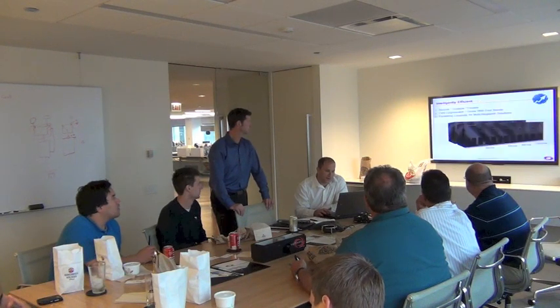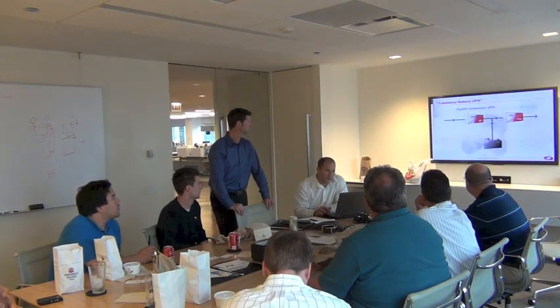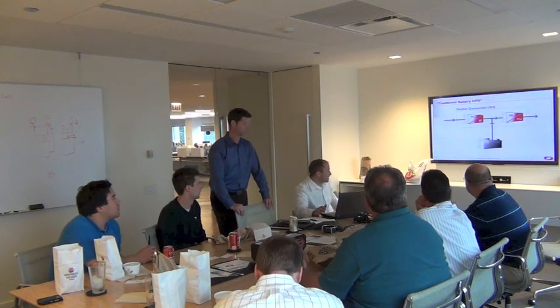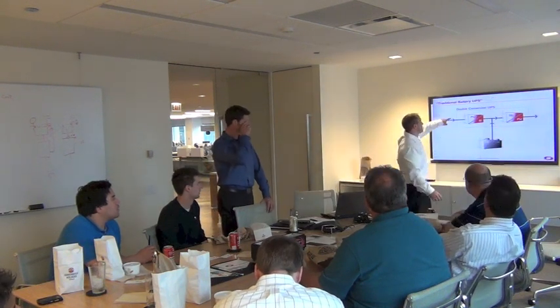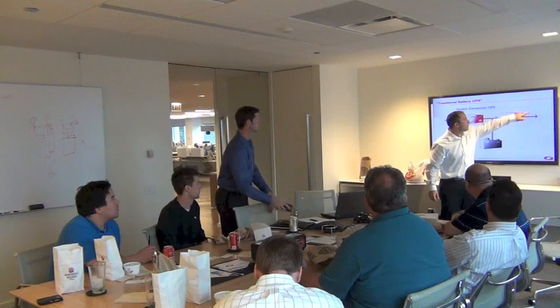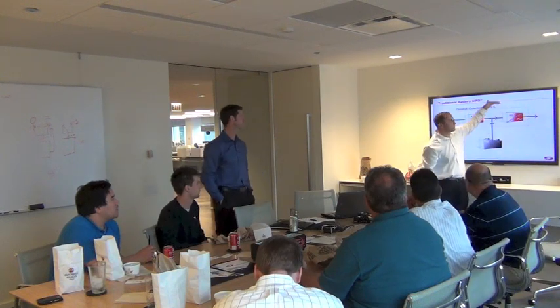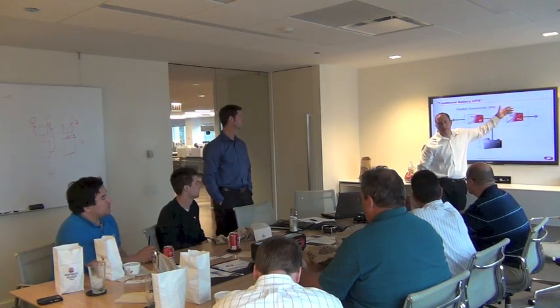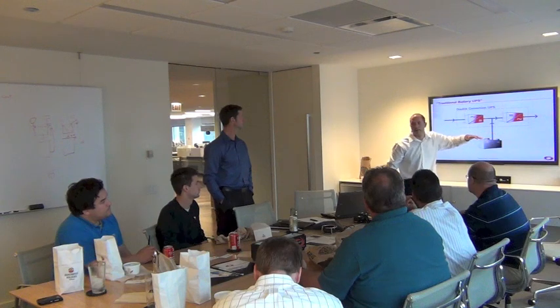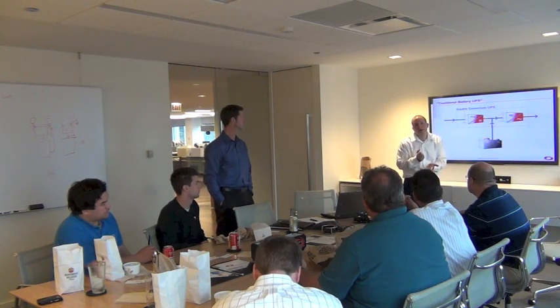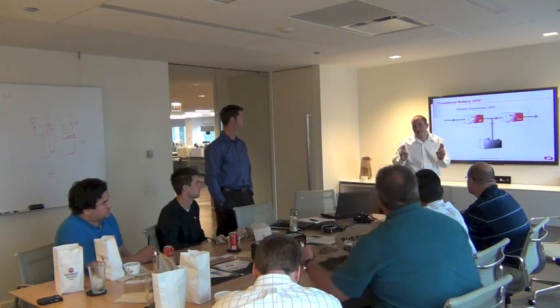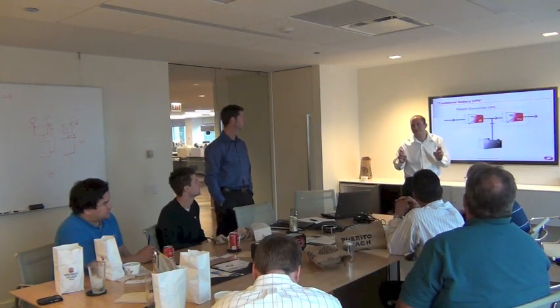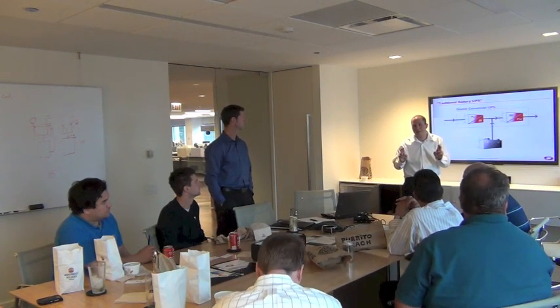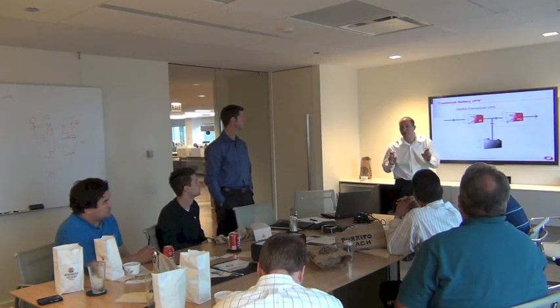of a double UPS. It's really high level, but basically in eco mode you have your static switch that wraps around here. All of your power is going through the static switch. In the event of an outage, you're switching back to online, basically. So one of the drawbacks may be that you're step loading your inverter every single time. There are some very high-tech engineers out there who have tested them and say there's a possibility they're not within the CBEMA curve. It depends on the outage.